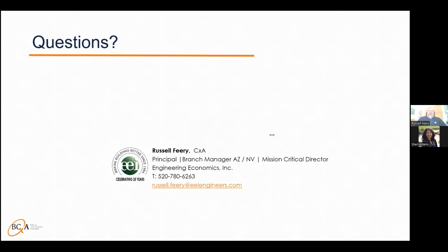Gotcha. Yeah, the envelope is the key to this. You would not want to have a chilled beam solution in a building that doesn't have a tight envelope. We've found that, or high humidity, that's the other issue, is the high humidity environment with a building envelope that is not tight could create a really big issue. And when you look at that link that I had for Titus, as they are talking about design considerations, they do go in depth into calculating the cost per square foot, the tonnage per square foot, and what some of the limitations are of chilled beams. In our climate in Arizona, it is a great cost-effective way, but we don't have to deal with high humidity environments.